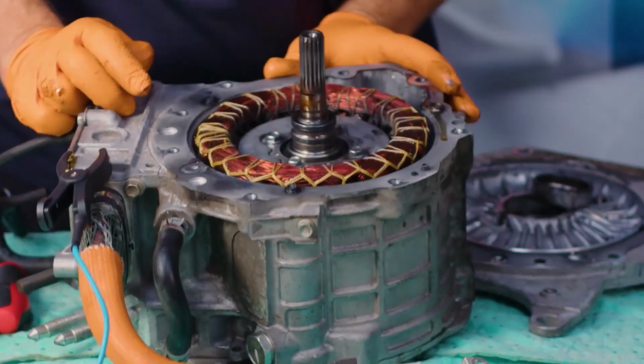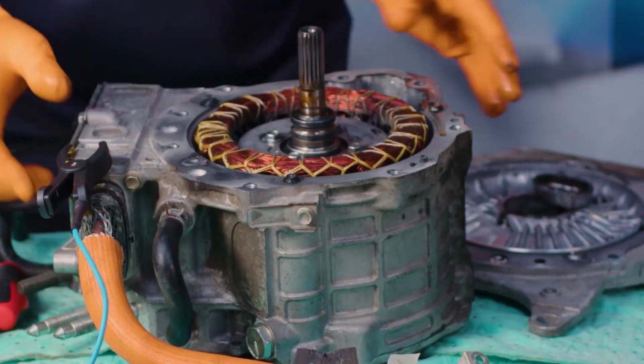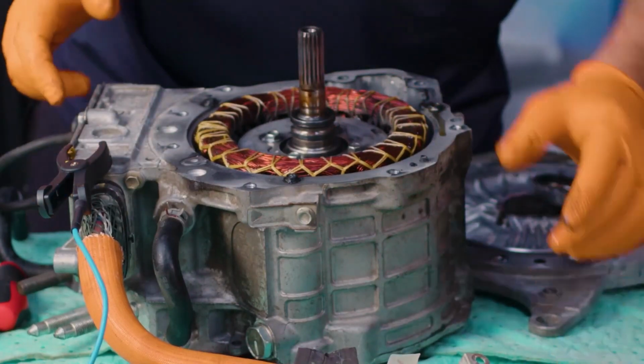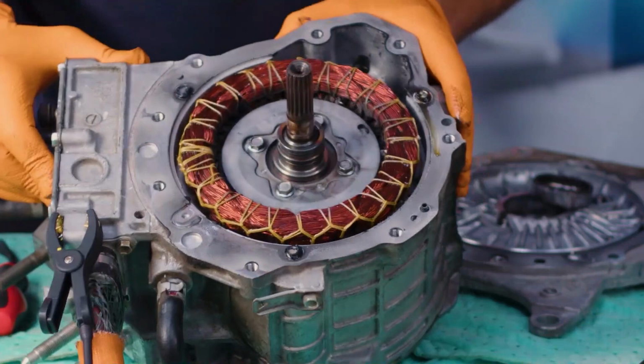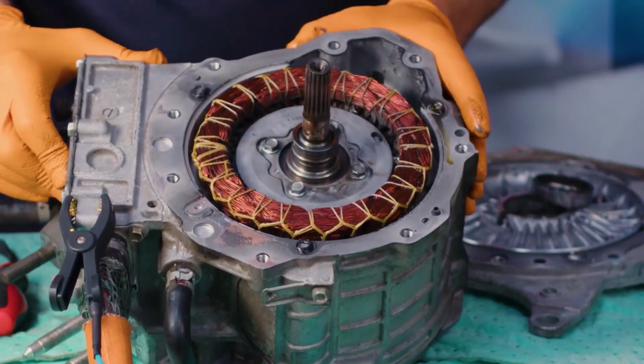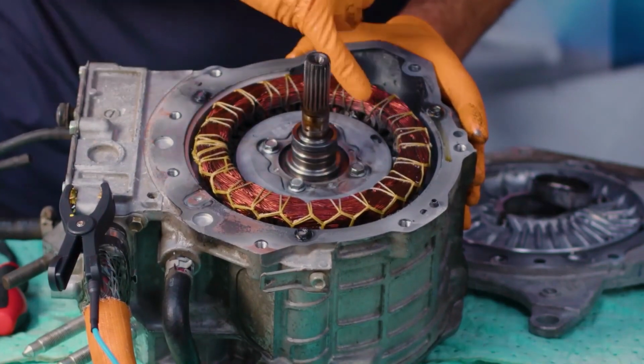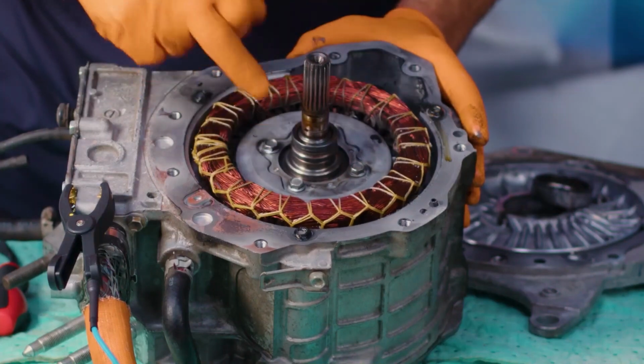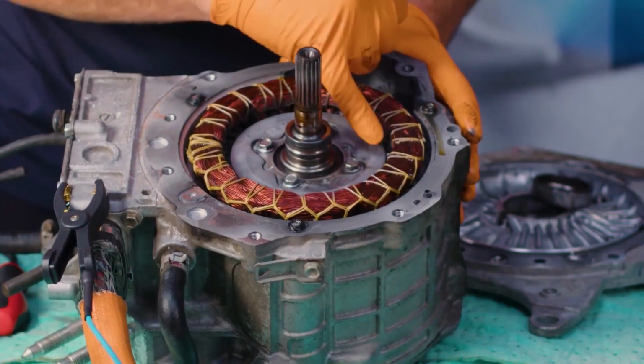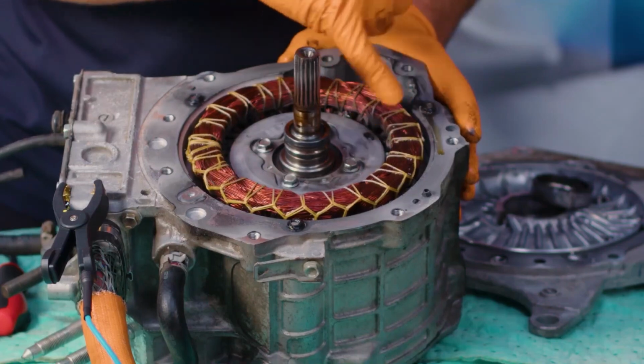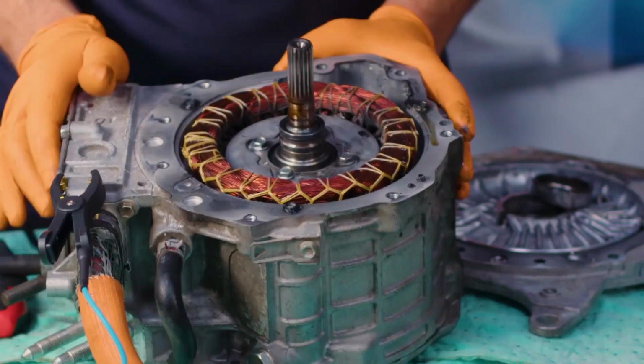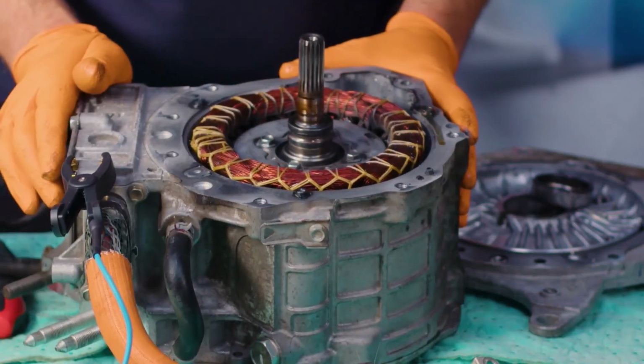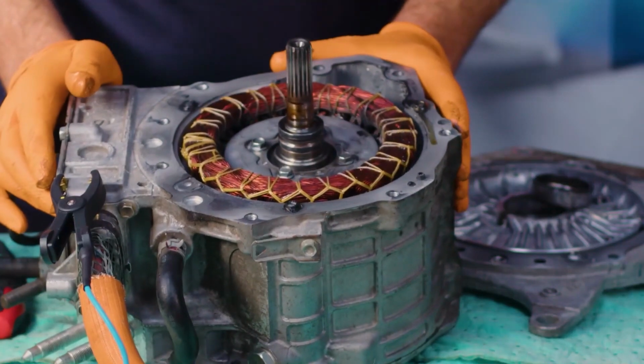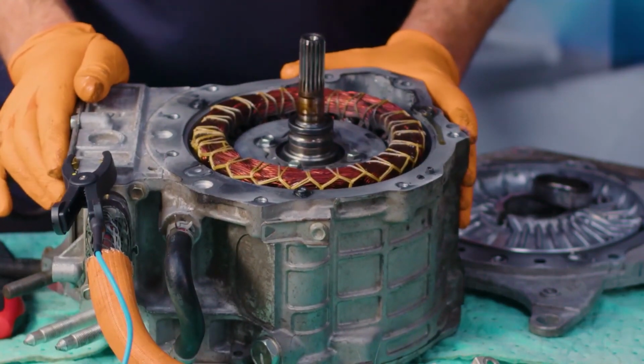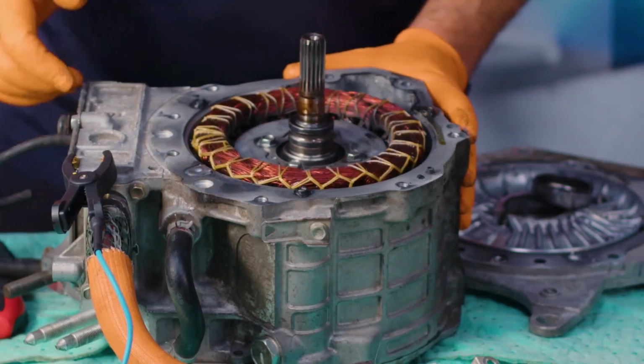In fact, now we are open circuit, which is exactly what we're after. So an open circuit there means we no longer have a short between the winding and the casing. With that said, there's obviously damage to the laminate around the coil, which unfortunately deems this non-serviceable. It'd be interesting to have a look at the insulation test now we've fetched that debris out, so we'll repeat the insulation test now.